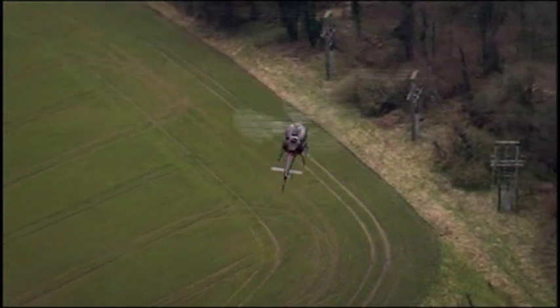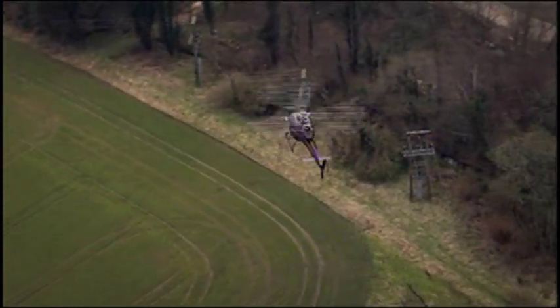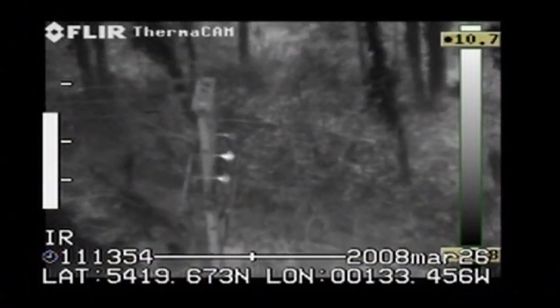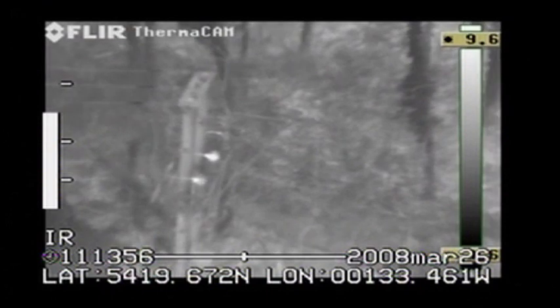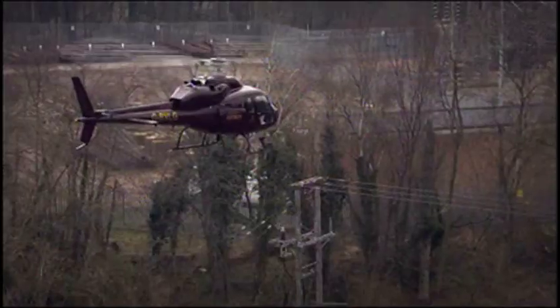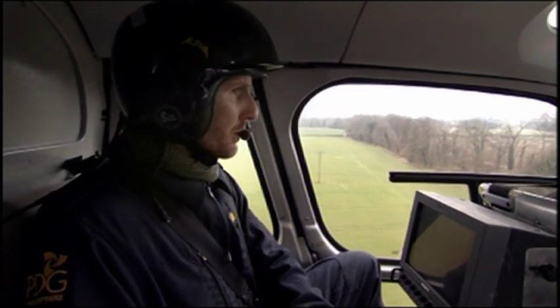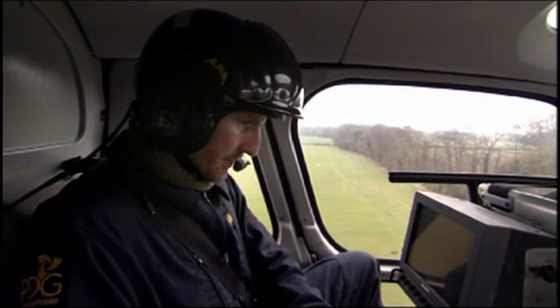I'm just panning the camera. Okay, we've got some hot spots here, actually, on the 33KV in front. There are multiple hot spots on this next one. Is it birds on the line? No, this is a hot spot on this one here. So if you take us in as close as you can, I think we probably want to go to the right just very slightly, minding for the trees.